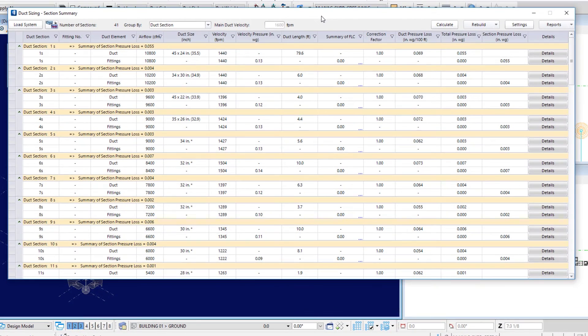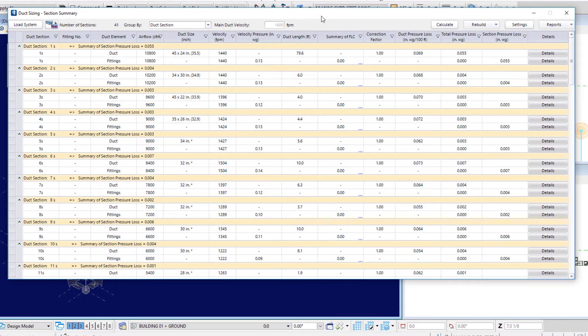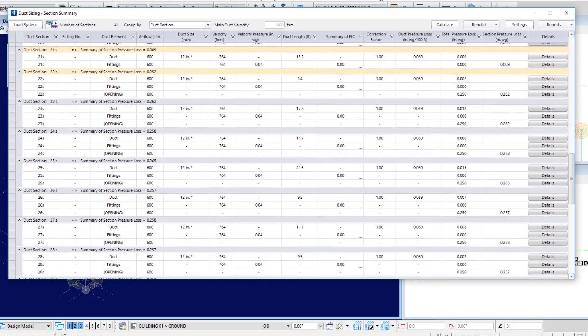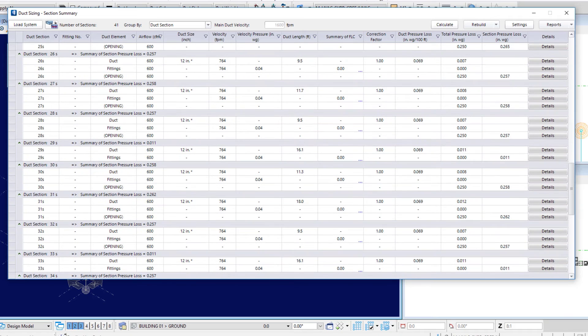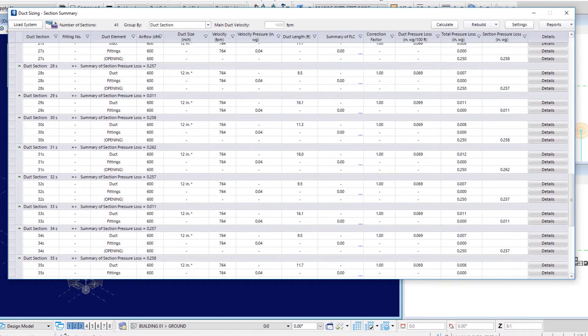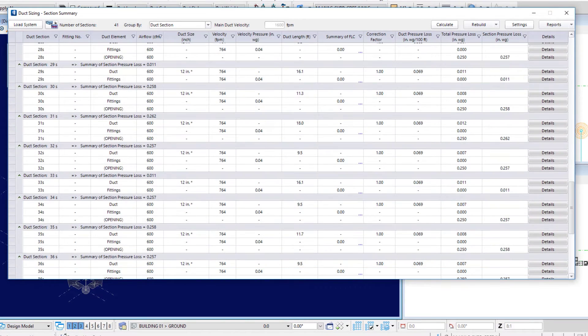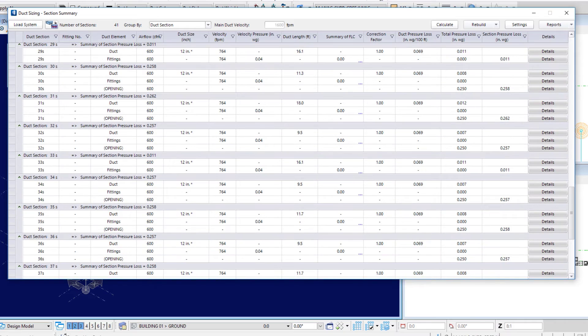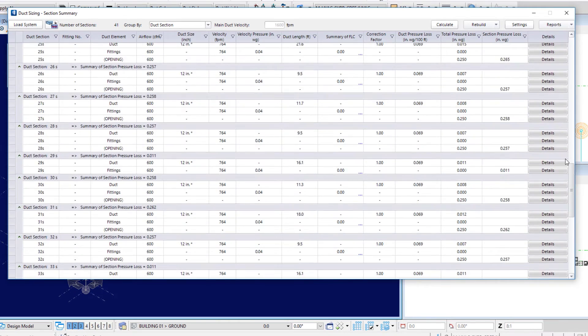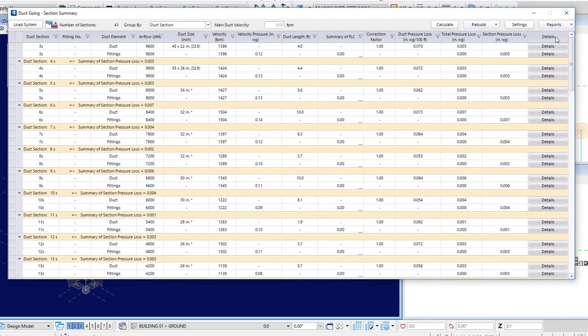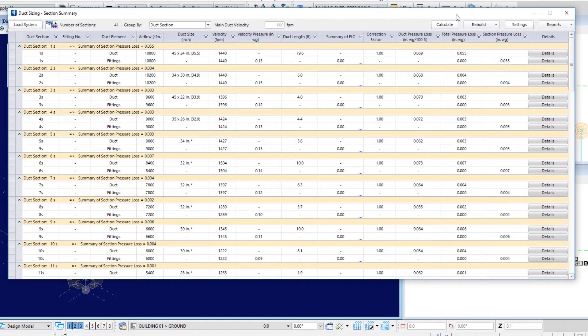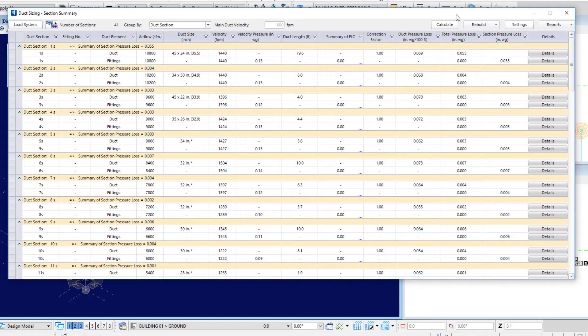And then we see our information is populated in here. So, we see that we have our different duct sections. And then it comes down to the air terminals. You can lock various properties in here and continue to calculate using the new sizes that you've locked. Either the width and depth, or you've locked the duct pressure loss for example.